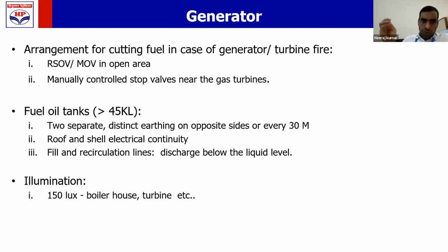In addition to this remote control valve, one manual control valve is also required. In case your remote control valve does not work, then how do you cut the fuel? A manual control valve shall also be provided, and that will be provided near the gas turbine. Sometimes you will need to close both your ROSOV and your manual control valve. Both need to be closed in case of a leak or so.